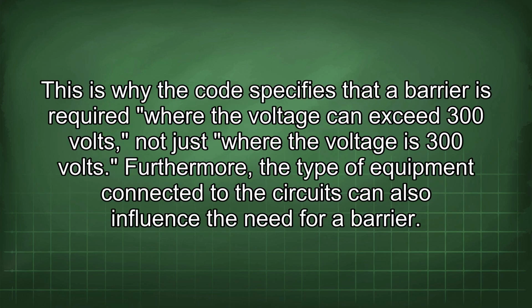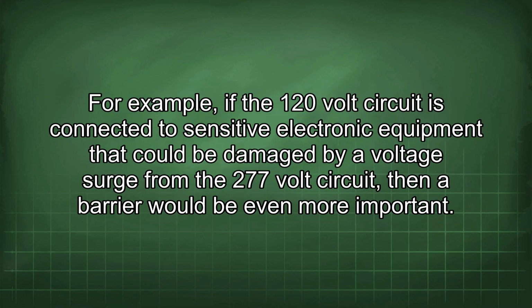This is why the code specifies that a barrier is required where the voltage can exceed 300 volts, not just where the voltage is 300 volts. Furthermore, the type of equipment connected to the circuits can also influence the need for a barrier. For example, if the 120-volt circuit is connected to sensitive electronic equipment that could be damaged by a voltage surge from the 277-volt circuit, then a barrier would be even more important.